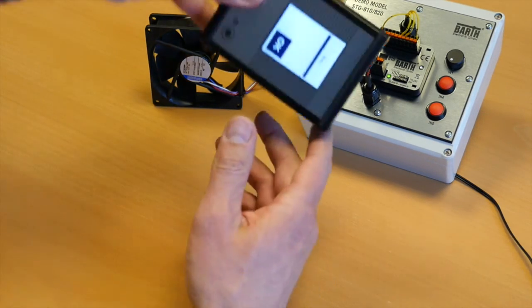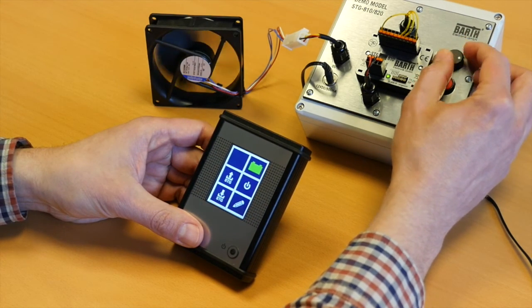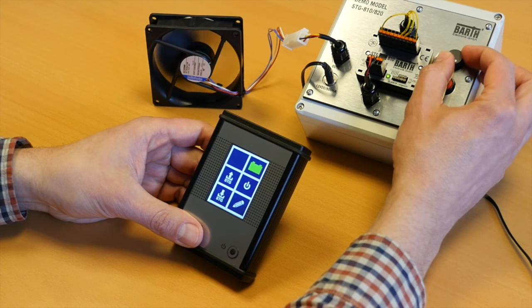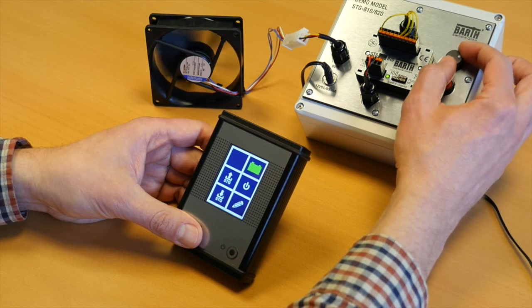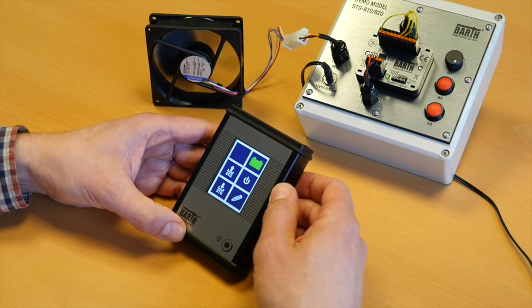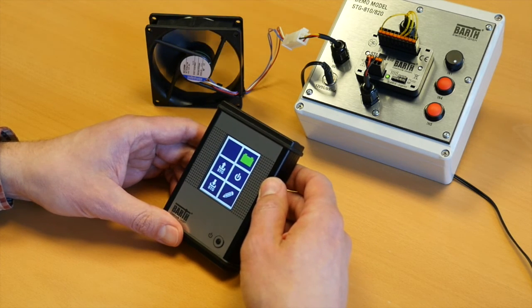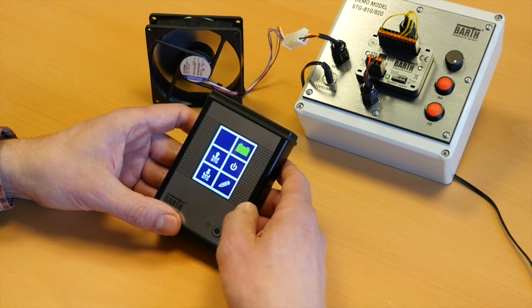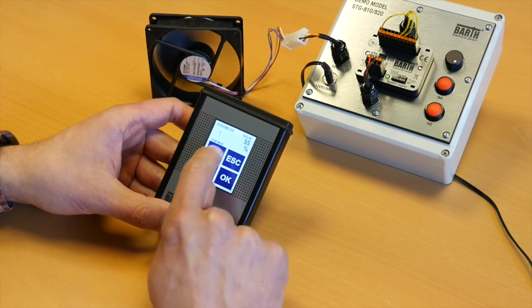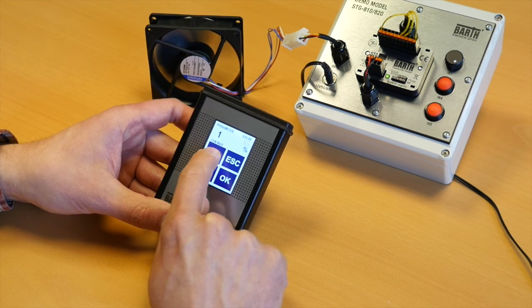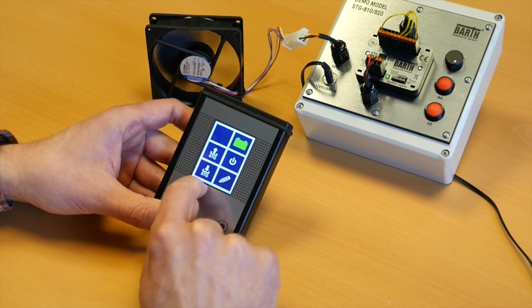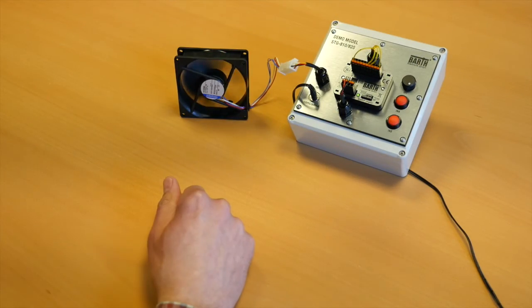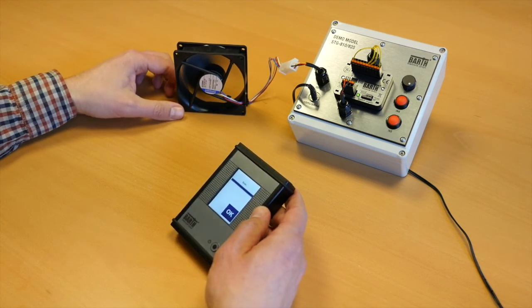Everything is done and now you are able to control the fan speed using the potentiometer. At 10 volts input voltage, the fan runs at 55%. If I want to achieve a higher speed, simply go into this parameter value by pressing OK. For example, go to 100%, confirm it, press escape and download it to the mini PLC. Now you can hear and see it, the fan runs at 100%.